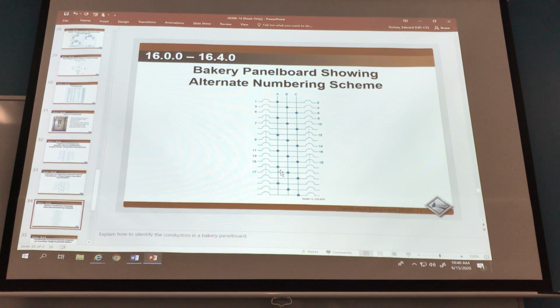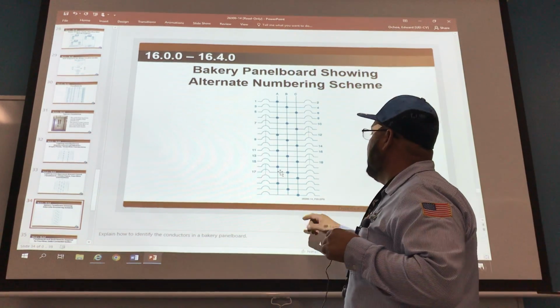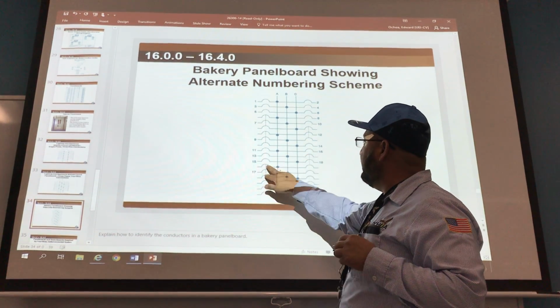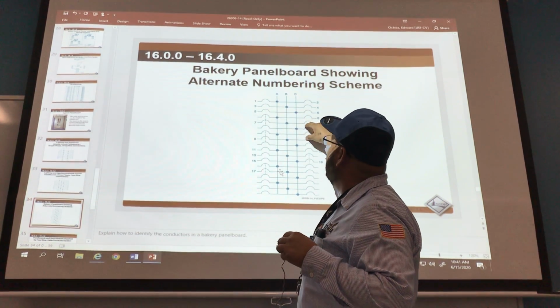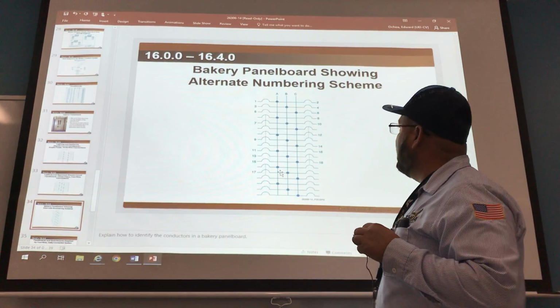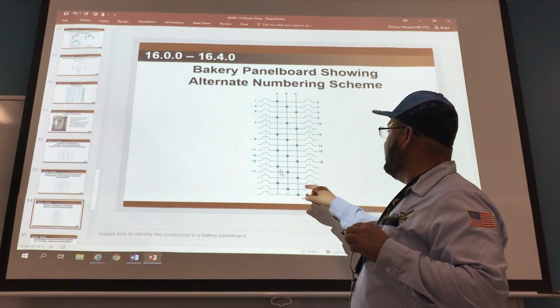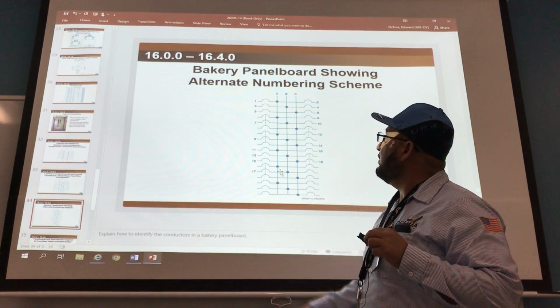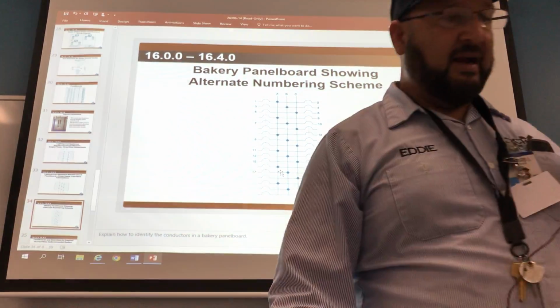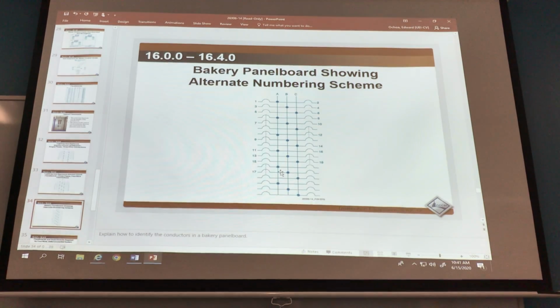Here's another phase system that we're working on. It's a typical 3-phase. If you use these 3 phases, they can be used for big bakery equipment. But the thing is, you have a B phase that's going to be a high leg. The high leg can be dangerous if you don't know that it exists. A lot of times you find high legs in older panels, older locations, or specified panels for certain buildings and businesses.